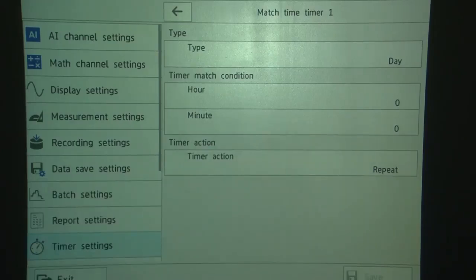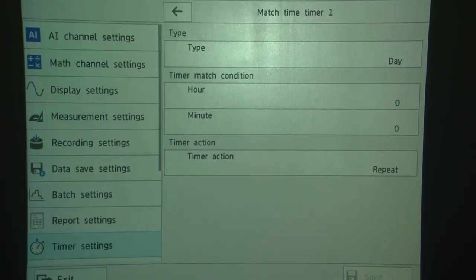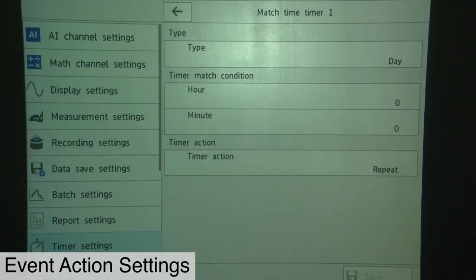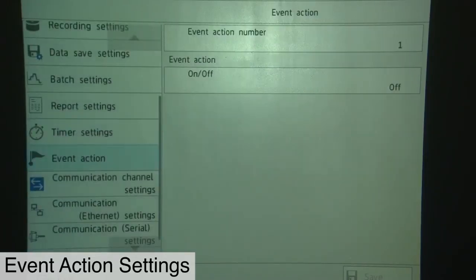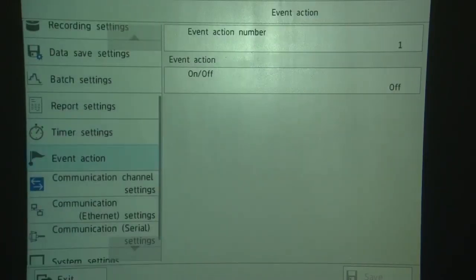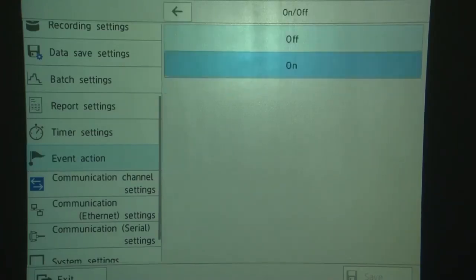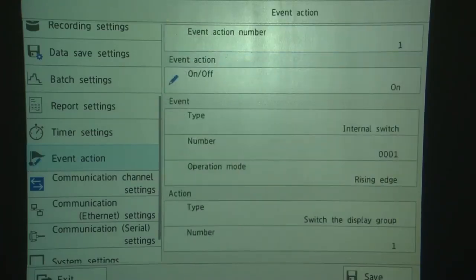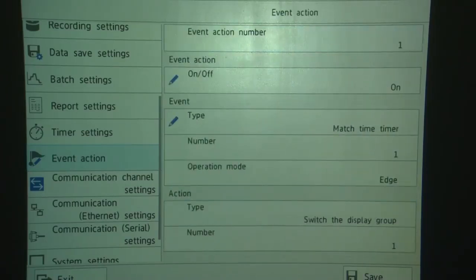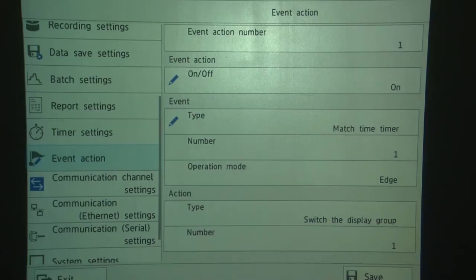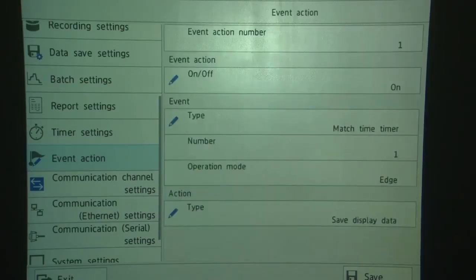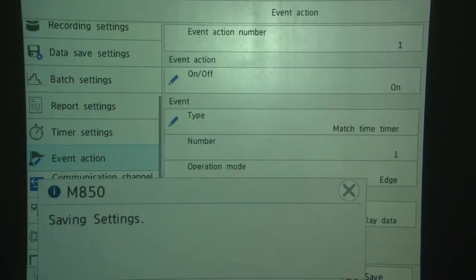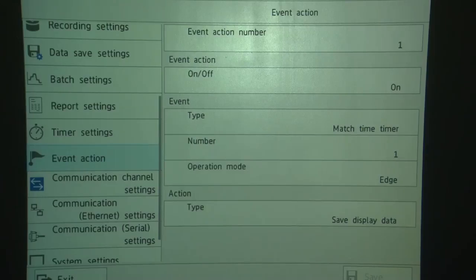So every 24 hours, the timer will expire. And we're going to use this as an event to trigger the display recording. The next thing we'll do is go to the event action settings. Touch Event Action. We're going to use the first event action. We're going to set that to on. We're going to set the type to match time timer. Timer 1 is going to be used. And then we're going to set the action to Save Display Data. Then we touch Save. And we're all ready to start recording. So now we touch Exit.